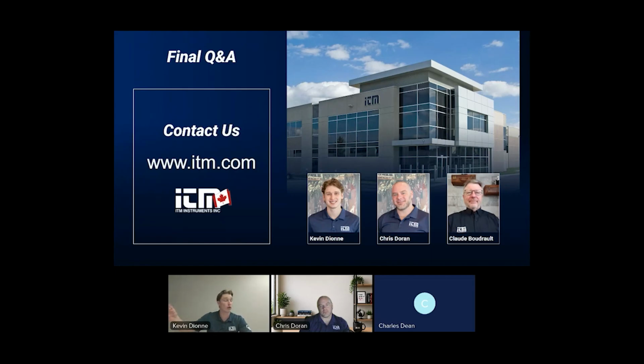Because if you're using a full scale gauge, whatever your accuracy percentage is will now be applied to the 0 to 1,000 rather than the 0 to 10,000. Hopefully I'm being clear. I'm not sure what your accuracy percentage is, but your instrument is going to be a lot more accurate when you're operating close to that 10,000 range relative to when you're operating at that 1,000 range, if you're using a full scale percentage, if that's the specification on your gauge.